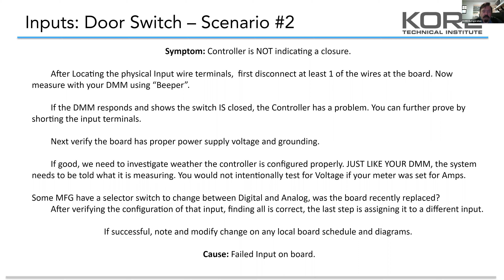Next, we need to verify that the board input power for the circuit board is actually getting the power it's supposed to receive. One of the very important key elements to any circuit board or control system being able to measure its inputs or outputs is having the proper power supply at its board in order to generate its signals. In this case, we're going to measure the power coming in and find that it's actually good. That means the system is not detecting its input or output properly. There are scenarios where you need to second-guess the controller — controller boards aren't infallible, they do go bad.